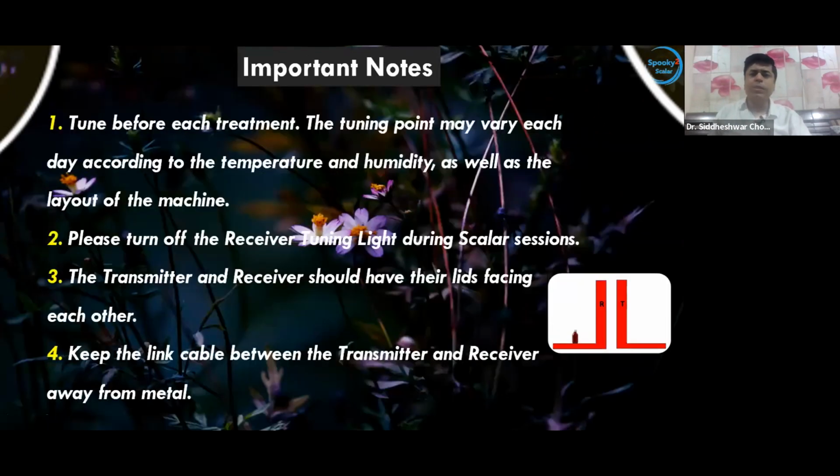Now, a few key points you have to understand are: tune before each session. Always tune before each session, because the tuning point can shift due to temperature or humidity, as well as the layout of the machine. What do I mean by layout? If you start increasing the distance between the transmitter and receiver coil, the frequency starts going down and down. Maybe 6 megahertz will become 5 megahertz now. It can go a little lower also if the distance between the lids is too large.